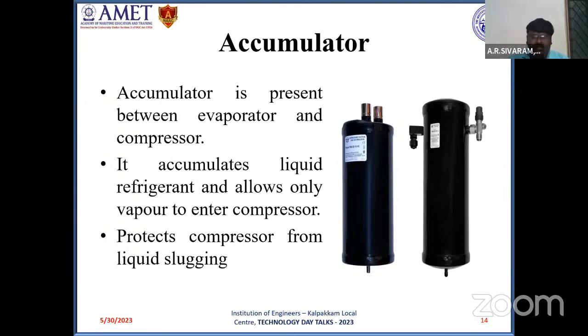And the accumulator is a component situated in between the evaporator outlet and the compressor inlet. The main function of this accumulator is this: if liquid refrigerant enters the compressor, it will cause liquid slugging of the compressor, which will result in failure of the compressor. In order to avoid that, the accumulator is placed between the evaporator outlet and compressor inlet. It accumulates the liquid refrigerant so that only vapor enters the compressor, and the liquid is accumulated within the accumulator and recycled back to the evaporator inlet.